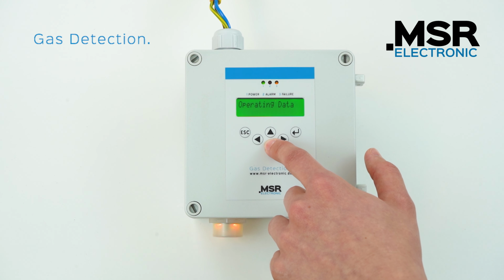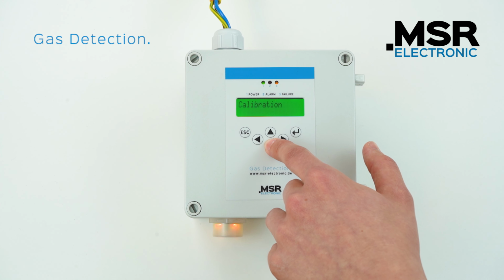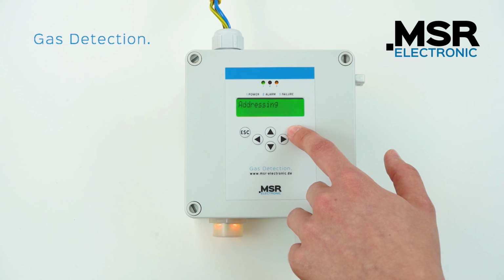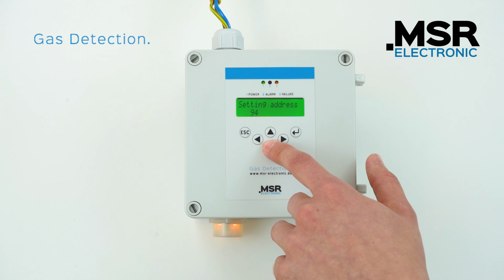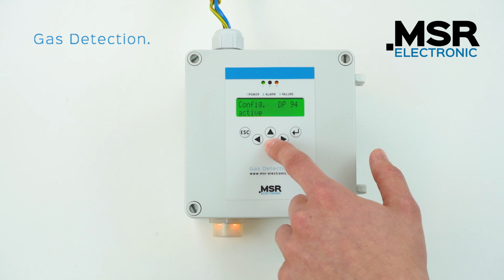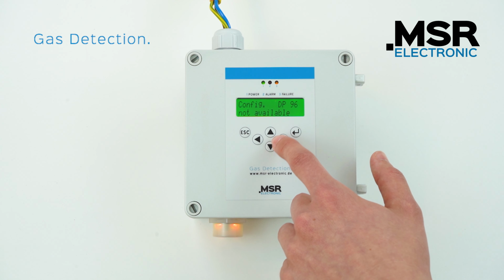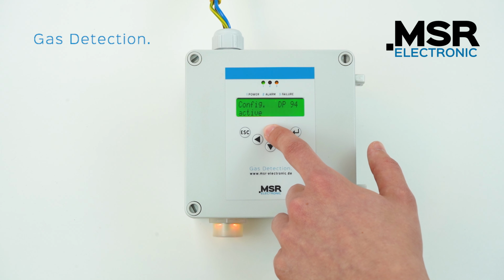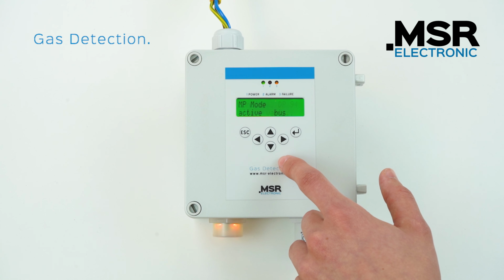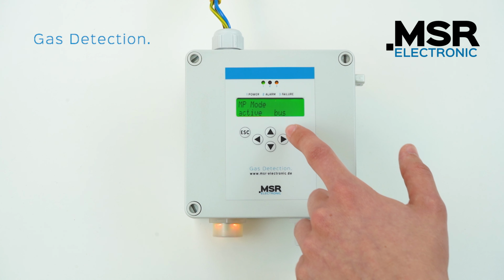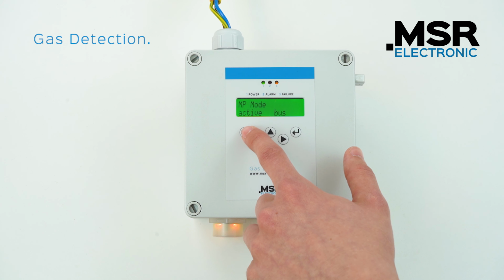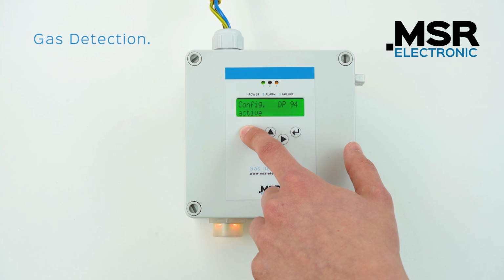Before we leave the service mode, we check the correct configuration in the addressing menu. Again, we select the correct address to which the sensor is connected. Then make sure that the address is configured to active and bus. If changes are made, save as before.